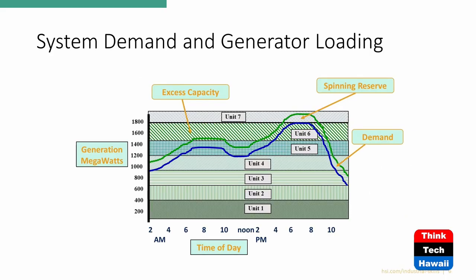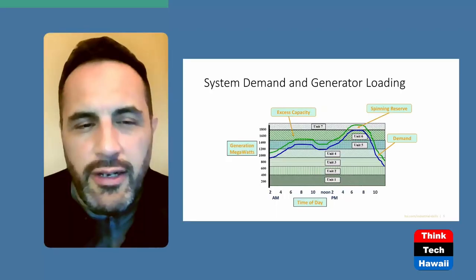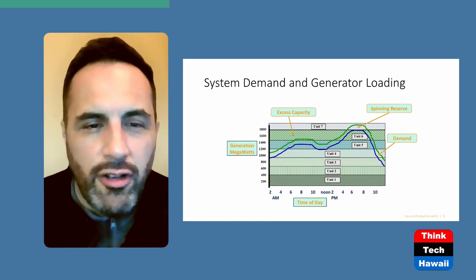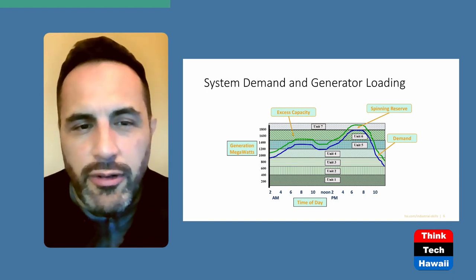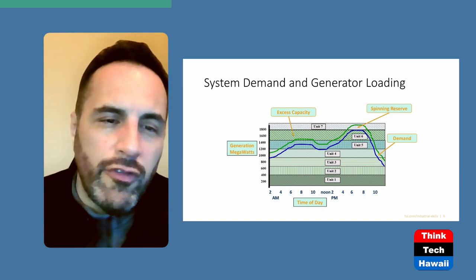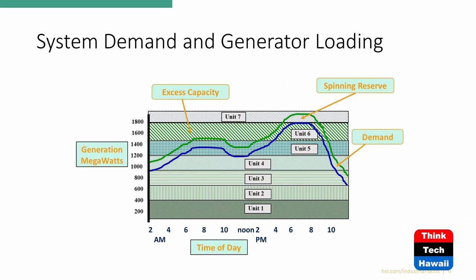This chart shows system demand and generator loading over a typical day — from midnight to midnight in two-hour increments. The load curve is shown in blue, generation capacity in green, and horizontal bars represent units one through seven, which run at different times depending on what's needed. Unit one runs pretty much all the time, as does unit two until midnight, when it backs down or shuts off. Units three and four back off or shut down as needed. Units five, six, and seven are run as needed.